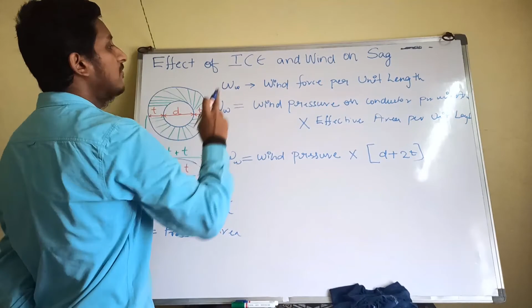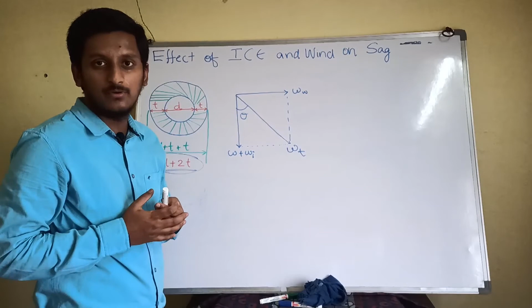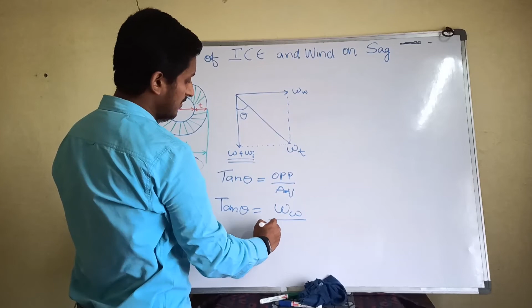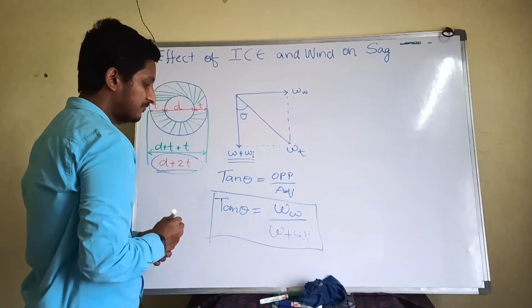We are going to see the slant sag and vertical sag formula. For that we have one more formula before that. See, this is theta angle. So when the conductor tries to settle down to its place, what will be the formula? That is tan theta is equal to opposite by adjacent. Now here opposite side is this part, and adjacent side is this part, as the angle is here. Now this opposite side is the same length of this one, Ww. So tan theta is equal to Ww, but the adjacent side is now this one. You can see it very clearly. Adjacent side is W plus Wi. You will get the angle at which the sag is going to settle down.